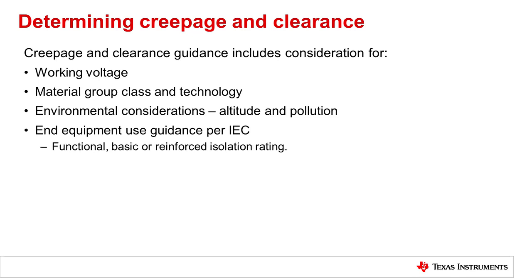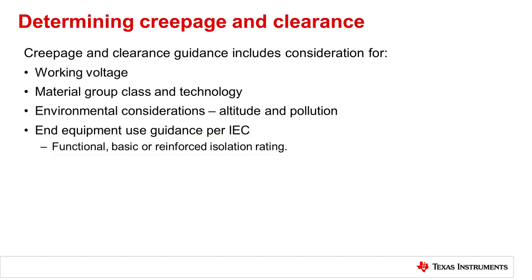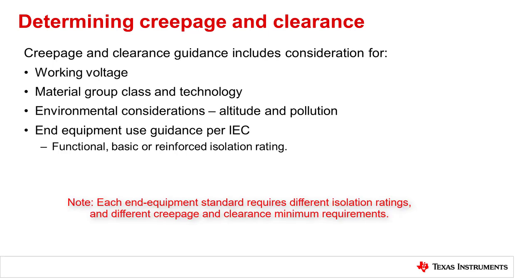The minimum distance for creepage and clearance will depend on whether the design requires functional, basic, or reinforced isolation ratings. These are the industry standard terms used to describe levels of voltage isolation performance and minimum safety requirements. The level of component isolation rating required is determined by the end equipment standards body — for example, the IEC standard for medical devices has different requirements than the standard used for test and measurement.